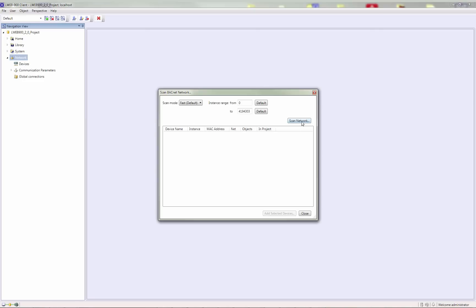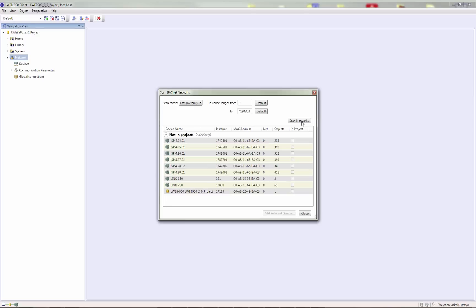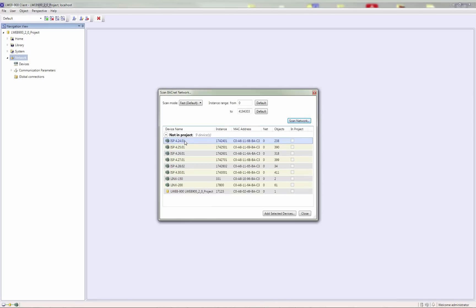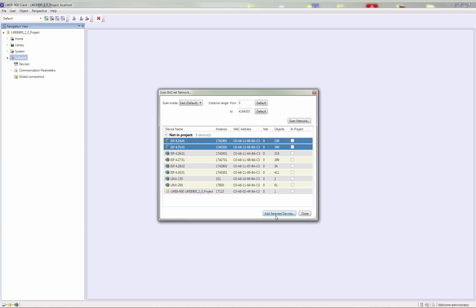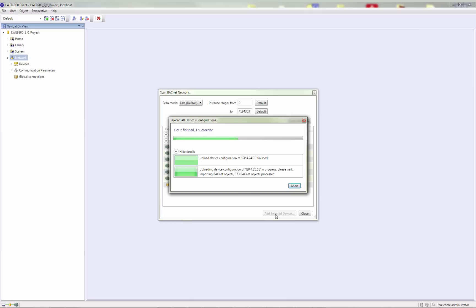Start the online scan and the LWEB900 server will search for devices on the BACnet network. All found devices will be shown in the device list. Select one or multiple devices and click the Add Selected Devices button. The server will read out the complete object list of the selected devices and add the new devices to the database.